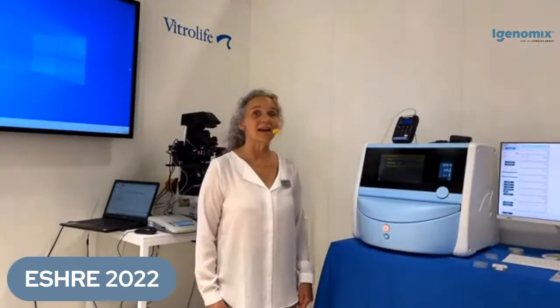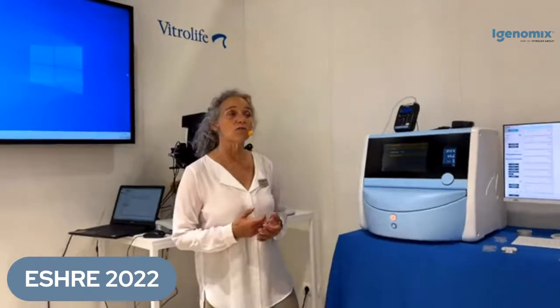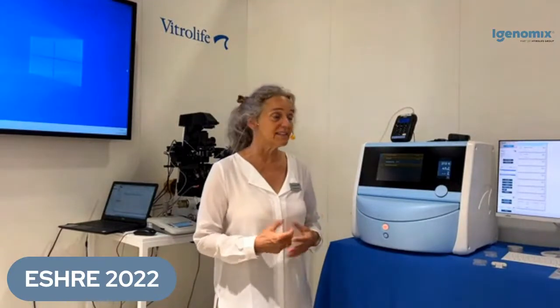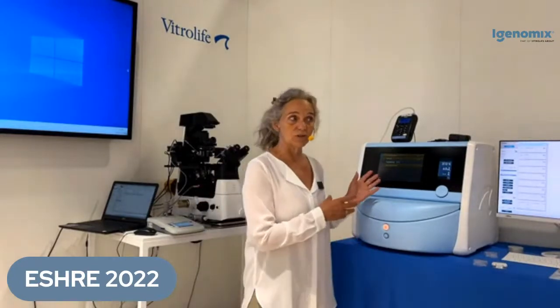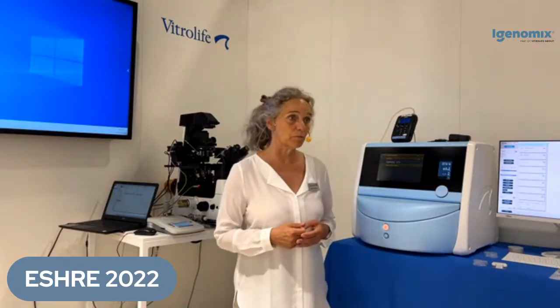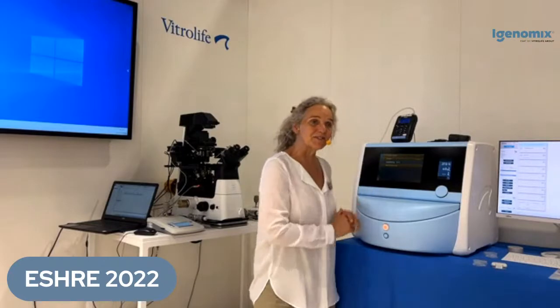Thanks, Reidun. As Tkun told you, I'm going to demonstrate how to validate the internal sensors, the gas sensors and the temperature sensors. And in case these are out of range, I'll show you how to calibrate the internal sensors. At the end of the session, we will also talk about how to perform pH measurement, and there are two options. The frequency of your validation: even though it's a very stable incubator, you still need to do your external validation on a regular basis.